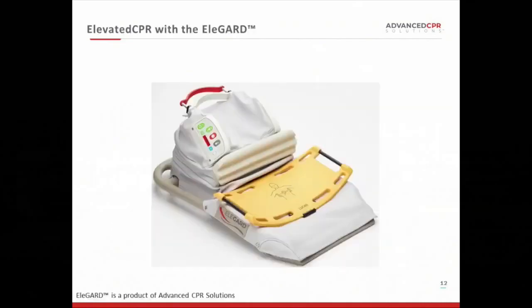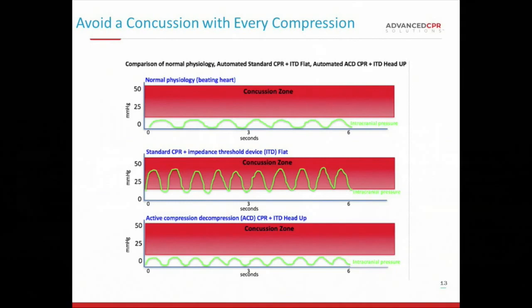Now we introduce elevated CPR with the EleGuard. This is a patient positioning device designed to be used with manual CPR, active compression decompression CPR, or the ITD. The Lucas back plate is already built into this device, and it is battery powered. You place the patient on it just as you're ready to start high-quality CPR, prime the pump for a couple of minutes, and then push a button to elevate the head to the optimal position. Using ACD-CPR with the ITD and the Lucas device, you can perform high-quality CPR with the head and thorax elevated and stay out of the concussion zone.